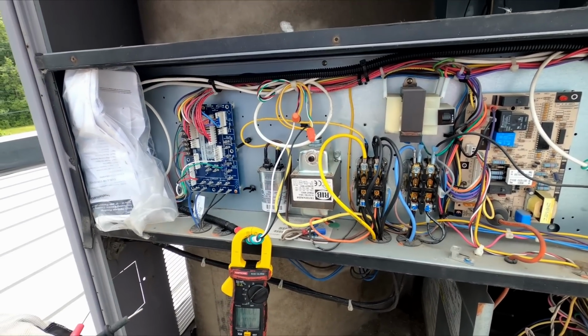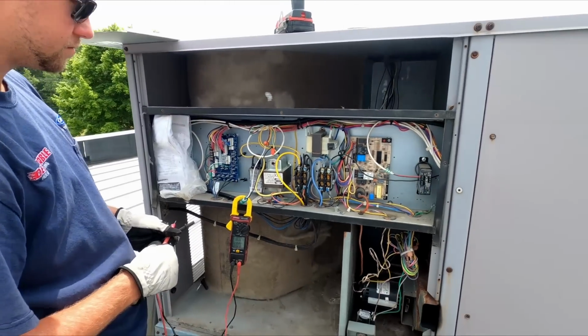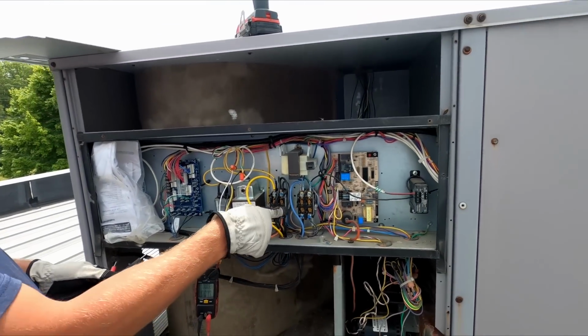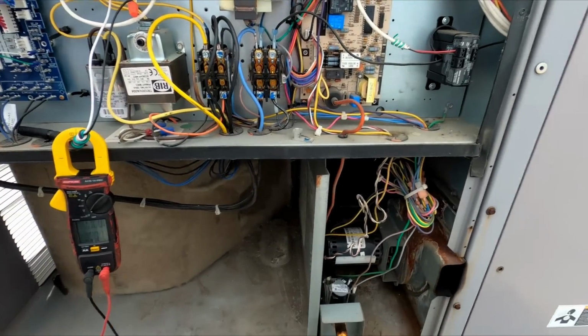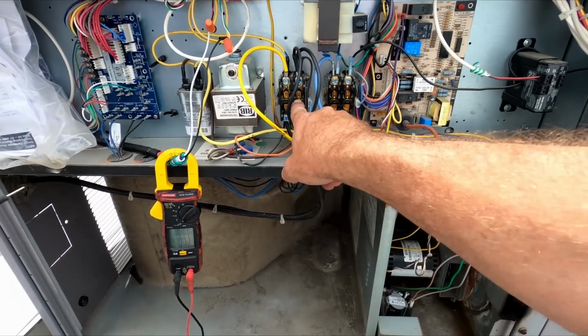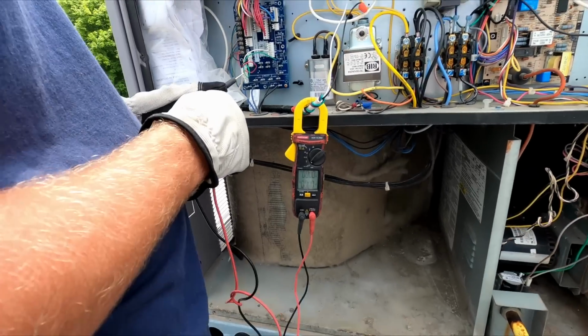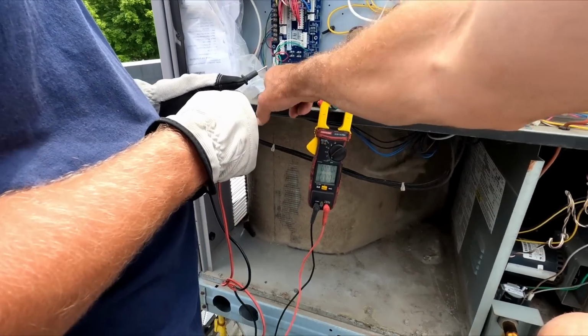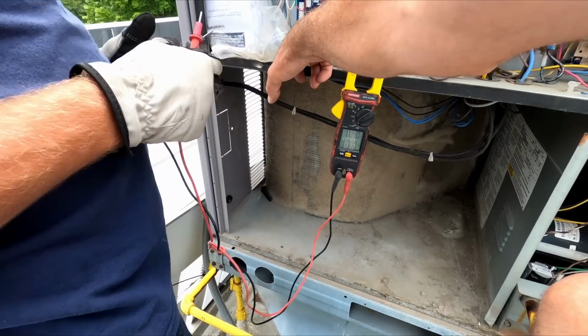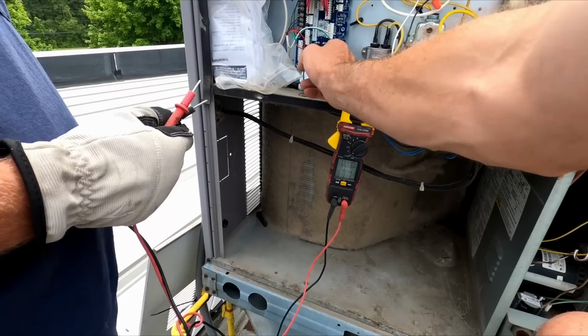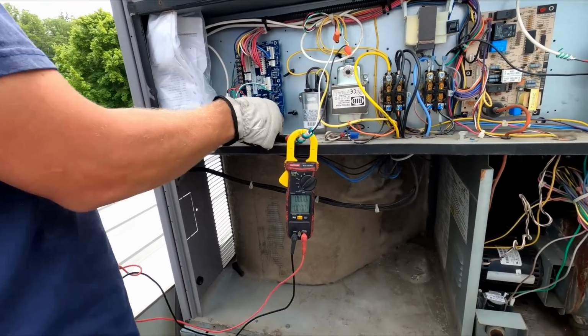Contactor. Okay, let's shut the power off. What just popped? Oh, that was the fan contactor. So our compressor contactor's here. So we got low pressure switch, high pressure switch. Pull those off, let's test continuity.